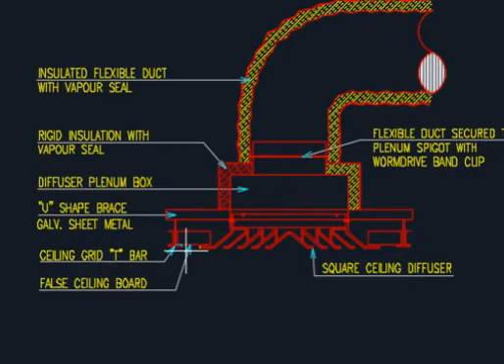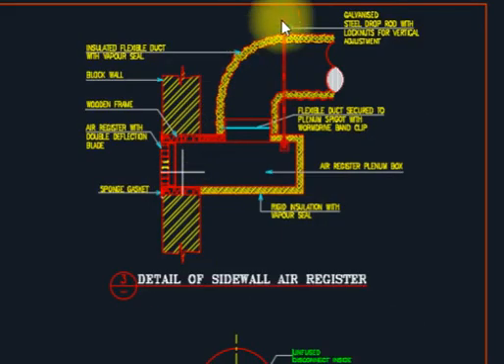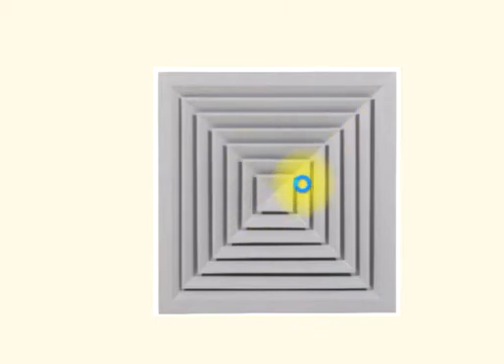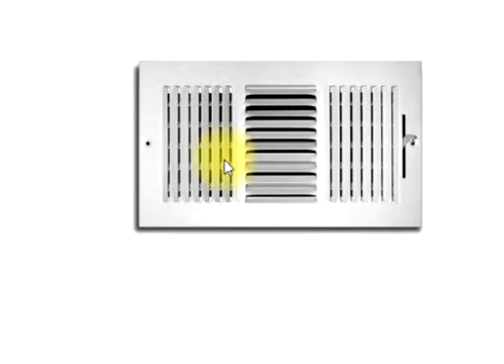So the diffuser will always be installed horizontally in the ceiling. Now this is a sidewall register — it will always come on the vertical wall. A register has a damper here which you can close or open. We use registers mostly in staircase pressurization fan areas, as well as in rooms and office areas. But mostly you will find them in staircase pressurization fan areas. You can remember: you can close or open the airflow by the register. A register is always vertical, not horizontal.